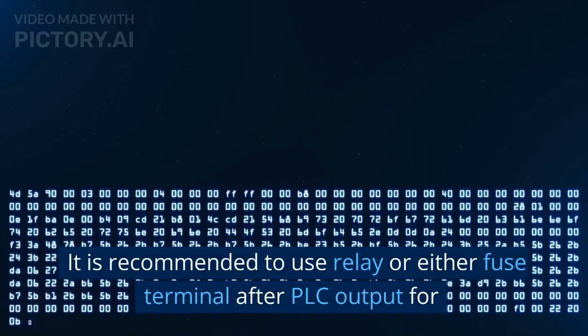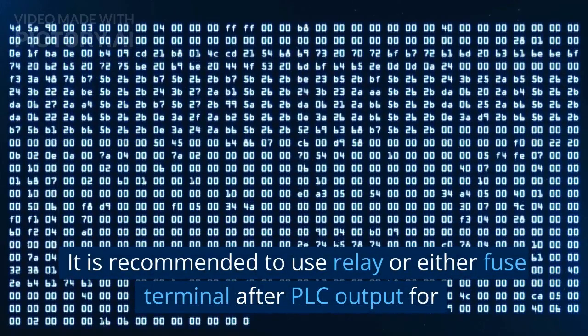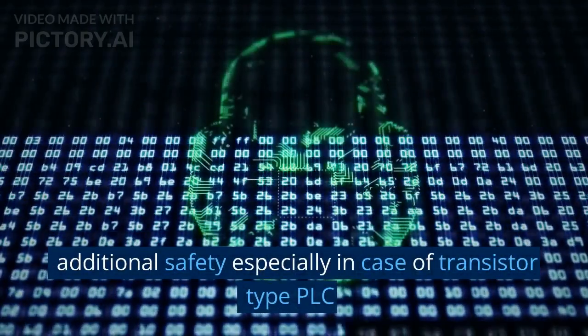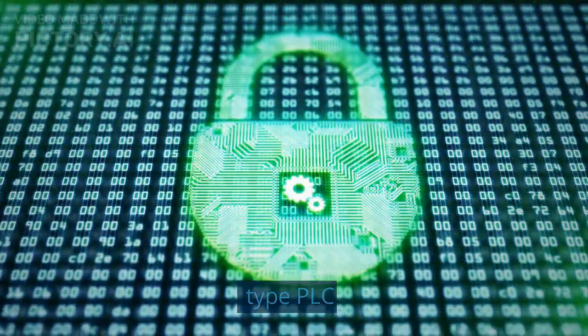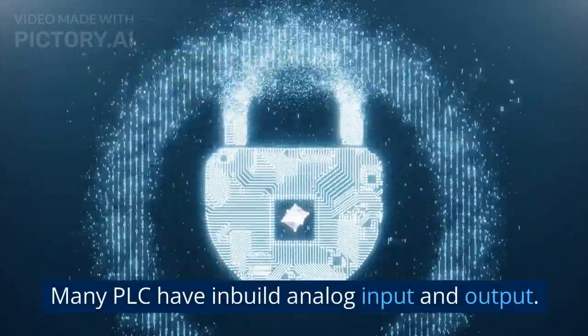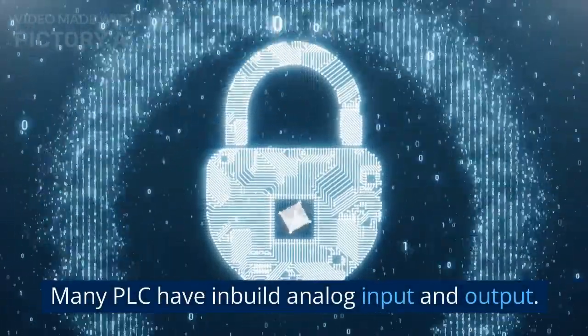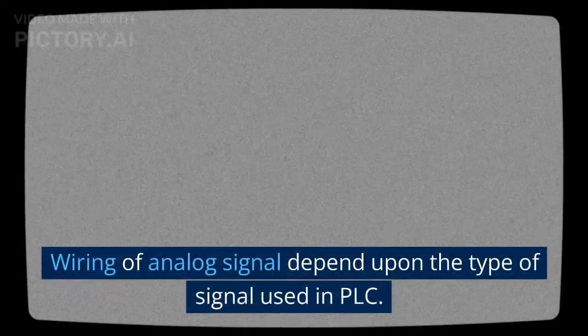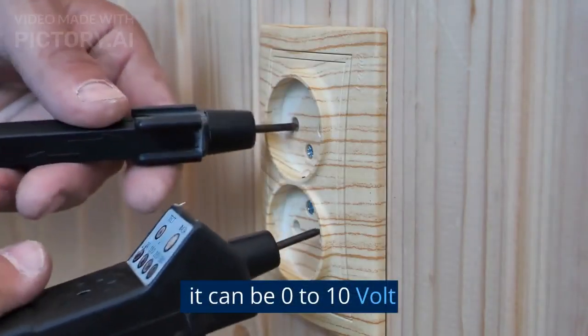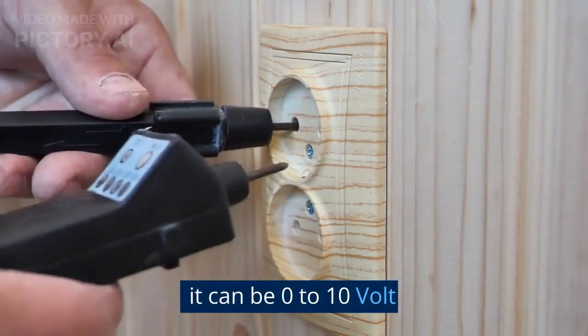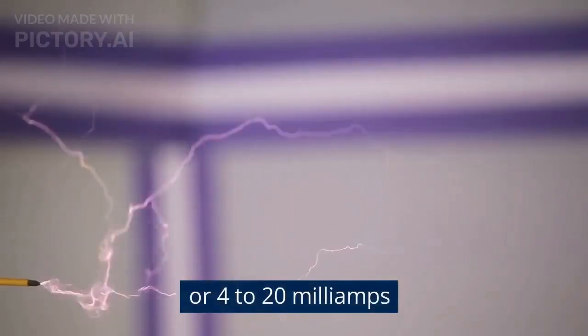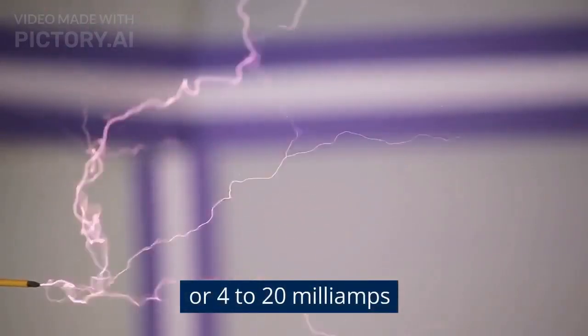It is recommended to use a relay or fuse terminal after the PLC output for additional safety, especially in case of a transistor type PLC. Many PLCs have inbuilt analog input and output functions. Wiring of analog signals depends upon the type of signal used in the PLC. It can be 0 to 10 volts or 4 to 20 milliamps. It is recommended to use general awareness while doing electrical wiring.